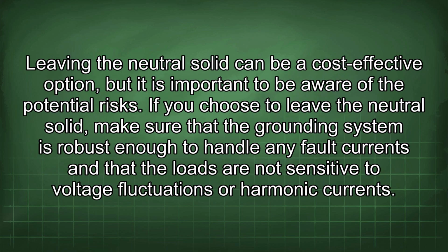Leaving the neutral solid can be a cost-effective option, but it is important to be aware of the potential risks. If you choose to leave the neutral solid, make sure that the grounding system is robust enough to handle any fault currents and that the loads are not sensitive to voltage fluctuations or harmonic currents.